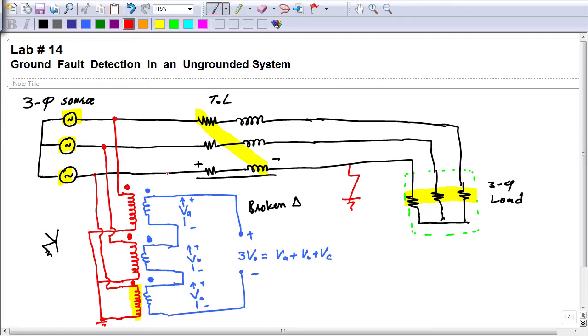And if this ground fault occurs before the transmission line, the voltage across the third VT will collapse to 0. So it means there will be a disturbance. Now the three voltages are not perfectly balanced, and their net sum gives us 3 times the zero sequence voltage. So the presence of voltage across the broken delta terminal is an indication that a line to ground fault has occurred in this ungrounded system. That voltage will be maximum right at the voltage transformer installation point, and will reduce as we move away from that point.